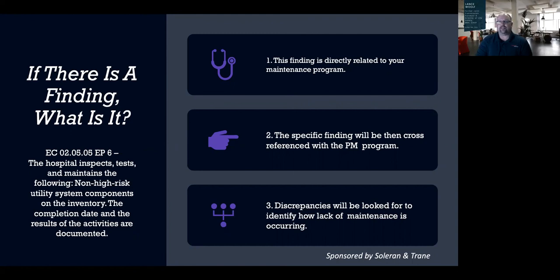Second, the specific finding is going to be cross-referenced to the PM program, as I talked about earlier. So I'm going to go back, follow that, look at your PM program, and then I'm also going to ask for your manufacturer's recommendations and cross-reference that as well, to make sure that you're following your manufacturer's recommendations. Now, if you're on an AEM program, then I'm going to ask you for a specific inventory list of your AEM program. And then I'm cross-referencing your chiller to your AEM program, and that it's identified on there what the risk rating is. But you're going to want to be able to speak to it if you are using an AEM program for your chiller. That's going to be the key: you're going to want to be able to back up the information and close that loop of why you decided to go against manufacturer's recommendations.